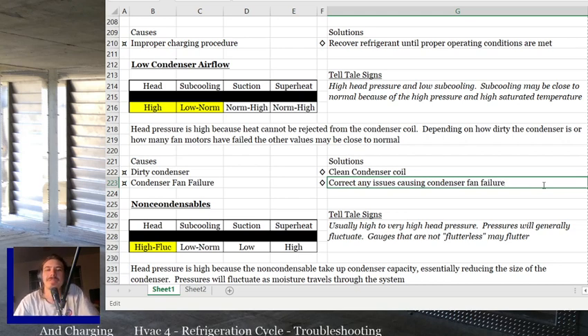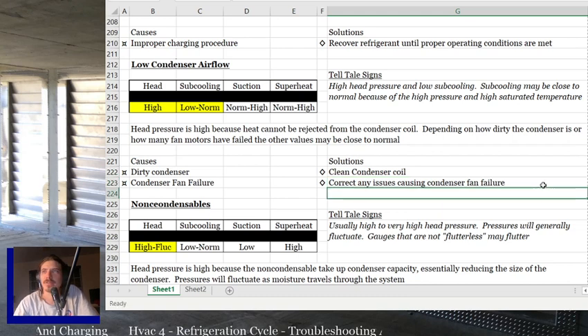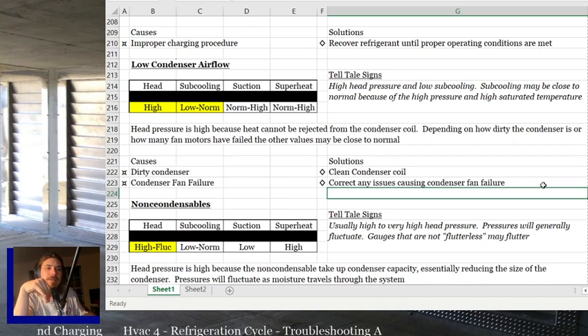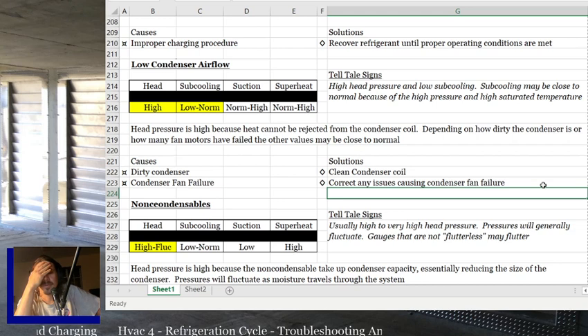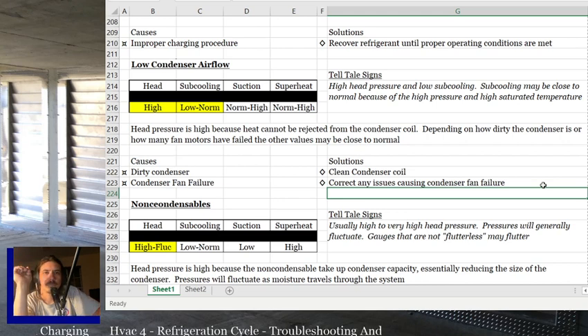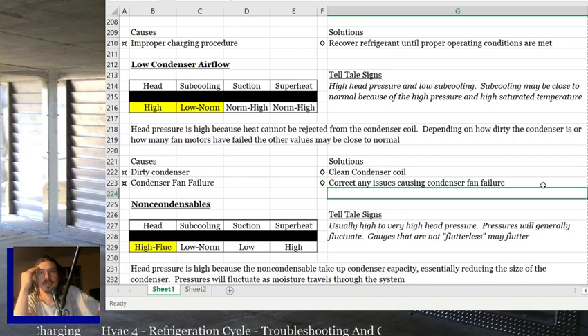One of the first times I ever tried to diagnose a failed TXV was actually just a dirty condenser. That's how weird they can look sometimes, right? Because your pressures are so high that you actually get really good subcooling sometimes. But anyway, the point is that head pressure is going to be pretty high. Everything else might look relatively normal with a dirty condenser. Usually it's pretty easy to spot either the failed fan motor or the packed condenser.